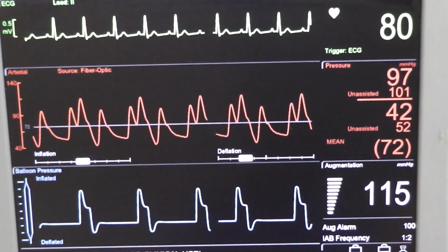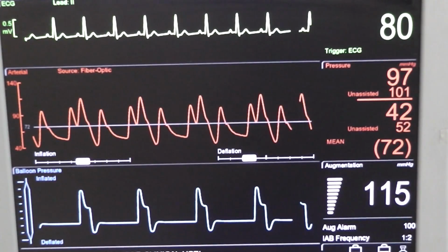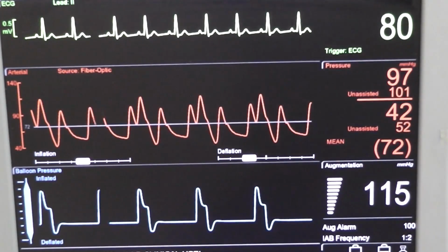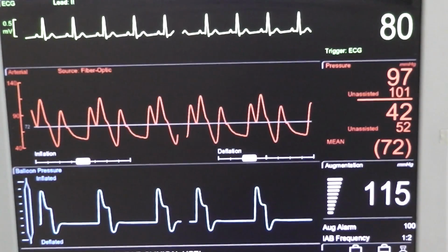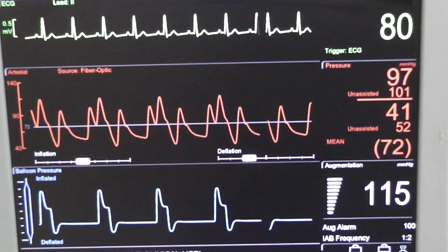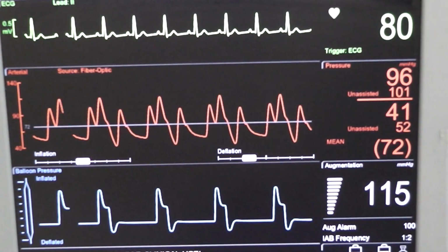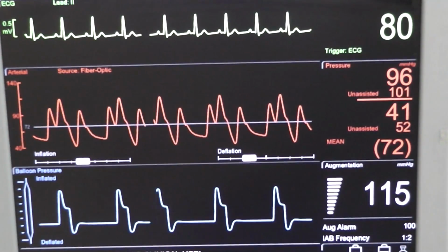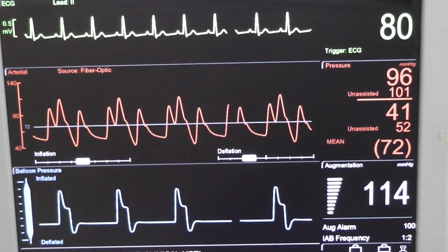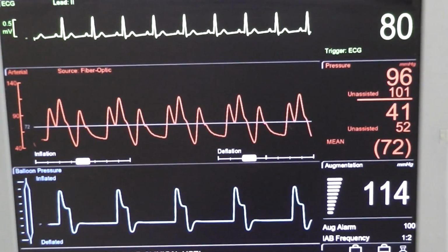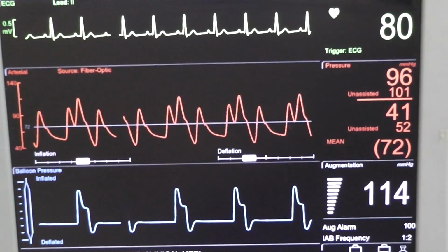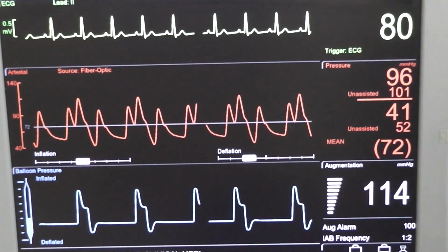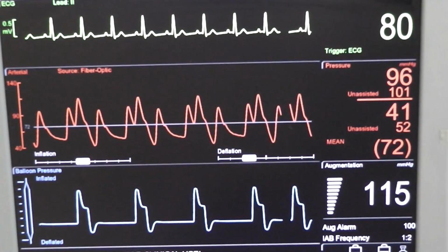Now we're back up to 42. So a couple clicks back to the right, and now we're back at 41. Should be roughly centered on that. So now we have perfectly timed inflation and deflation, and this is going to be the most optimal position for this to be set at for our patient.